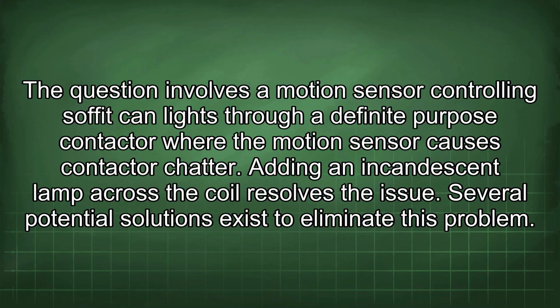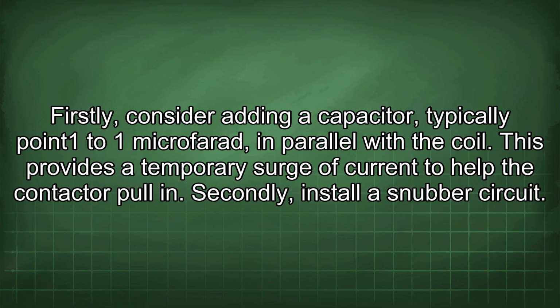The question involves a motion sensor controlling soffit can lights through a definite purpose contactor, where the motion sensor causes contactor chatter. Adding an incandescent lamp across the coil resolves the issue. Several potential solutions exist to eliminate this problem. Firstly, consider adding a capacitor, typically 0.1 to 1 microfarad, in parallel with the coil. This provides a temporary surge of current to help the contactor pull in.